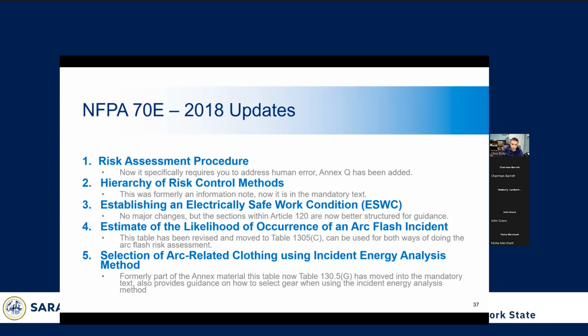This is all having to do with the risk assessment procedure. The NFPA 70E outlines procedures to reduce the risk for inspectors and electrical workers. And so what this encompasses is it gives you a risk assessment procedure. You would want to go through the hierarchy of risk control methods, which we'll go over on the next slide. It gives you information on how to establish an electrically safe work condition.